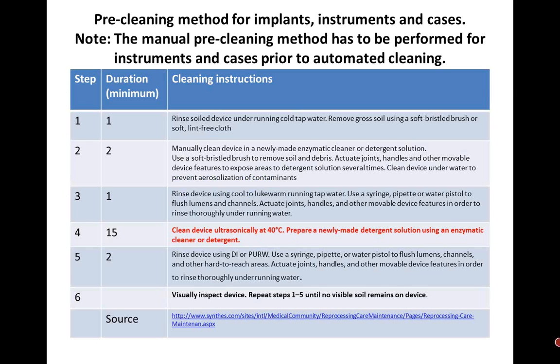This here is actually taken from an IFU, and you see the source there. It's one of many companies, and I've used this as an example as part of their cleaning process. If you add all the time up, you get 15, 16, 17, 18, 20 some plus minutes as part of the cleaning process. But if you look at what's highlighted, this IFU states you should have a minimum of 15 minutes to clean those items at a temperature around 40 C and prepare newly made detergent solution using an enzymatic cleaner or an appropriate detergent. So this IFU states this is how you need to clean the implants, instruments, and the cases.